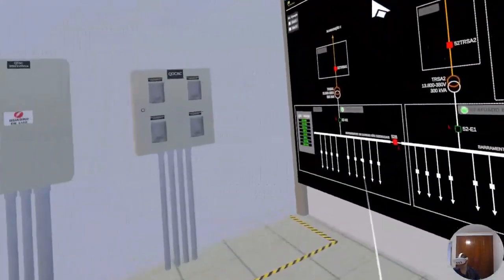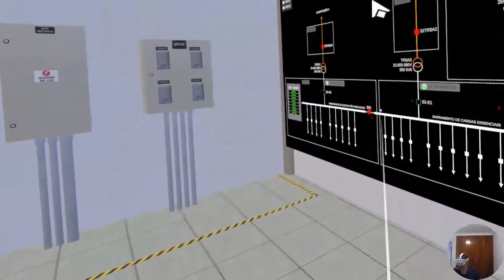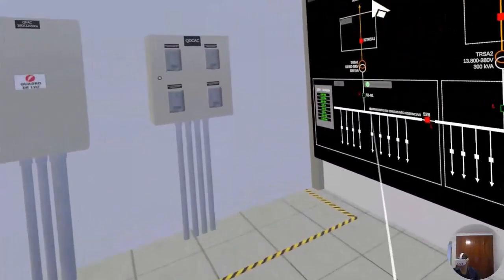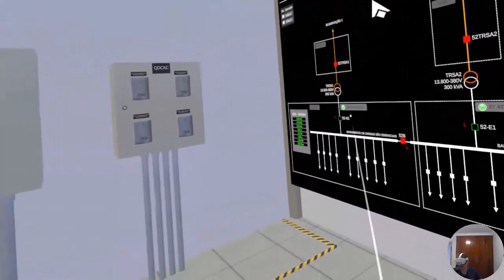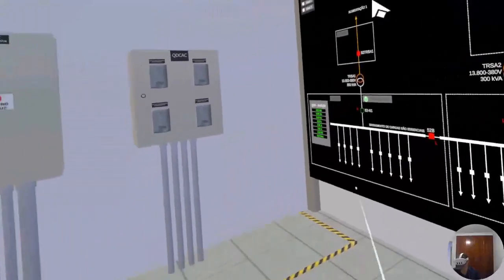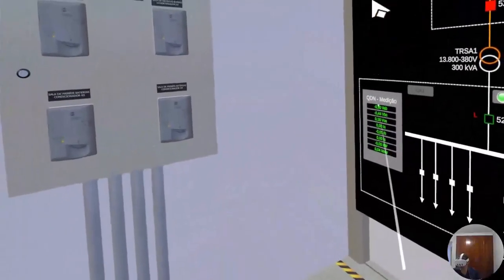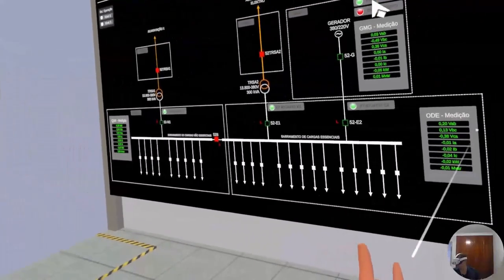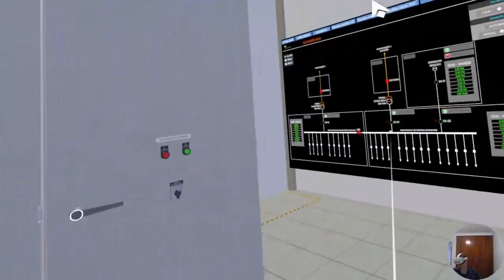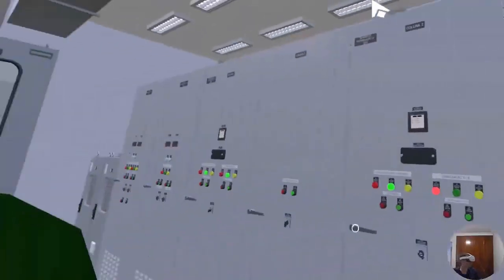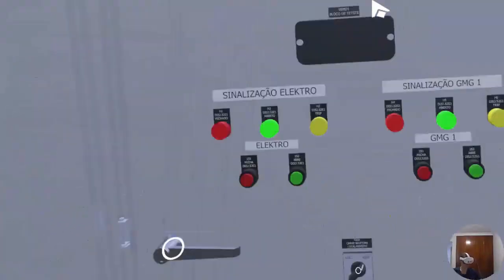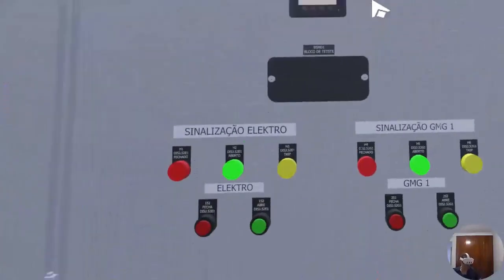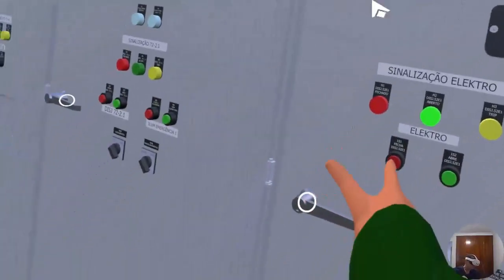I've opened it. 0 volts. When I turned the key to local, I signaled local here on the circuit breakers. Now I can no longer operate them from here remotely. I'm at 0, I'm at 0, I'm at 0. And now, everyone, just so you know, I'm going to go ahead and bring in feed 2. I come here, and then I switch to local mode, making sure everything is set correctly, and after that, I turn on this circuit breaker.